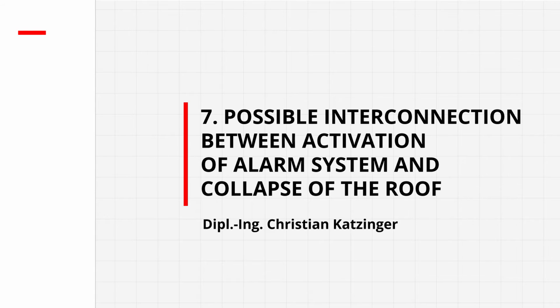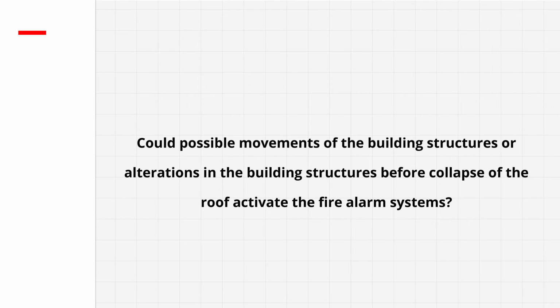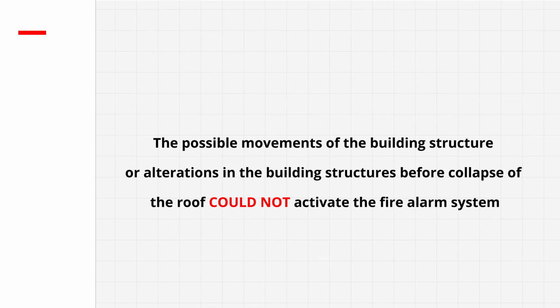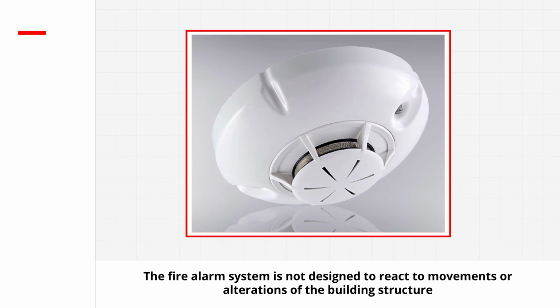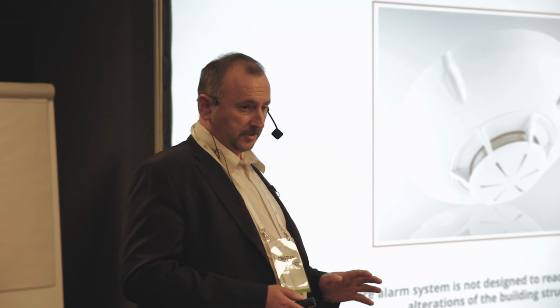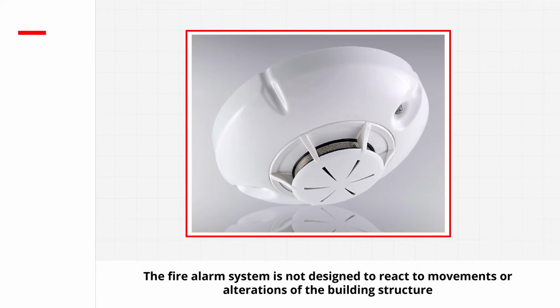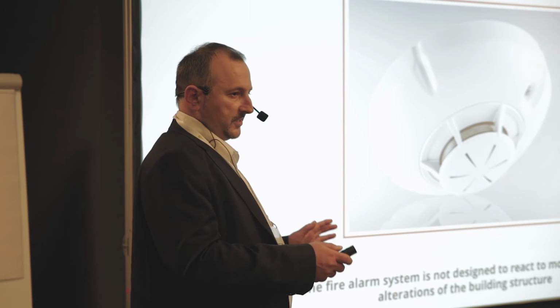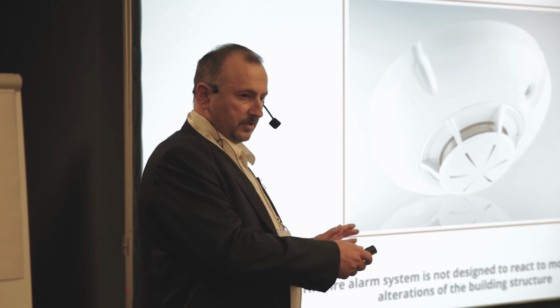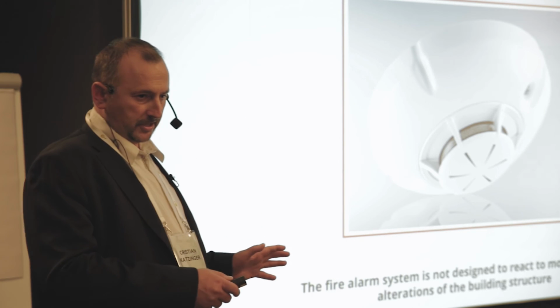Could there be possible interconnections between the activation of the fire alarm system and the collapse of the roof? Could possible movements of the building structure or alterations in the building structure before the collapse of the roof activate the fire alarm system? We can say no, it could not. We have a fire detection system, not a movement detection system. It is an automatic fire detection system with smoke detectors. A loose contact or a break of wires wouldn't cause any fire alarm. It would just send a failure to the control unit: look, there's a mistake, please check it, change it.